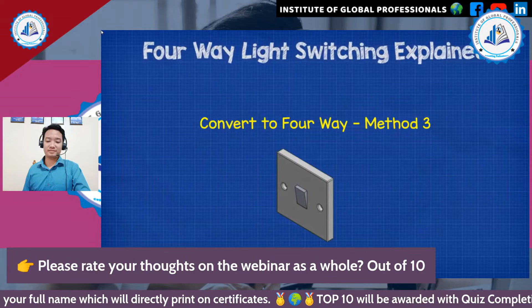In this design, we bring the power and the lamp control to the rightmost switch. We run a brown wire from L1 of switch 3 to L1 of switch 2, then another brown wire from L3 of switch 2 to L2 of switch 1. We run a grey wire from the common of switch 1 to the common of switch 3, then a black wire from L2 of switch 3 to L2 of switch 2.